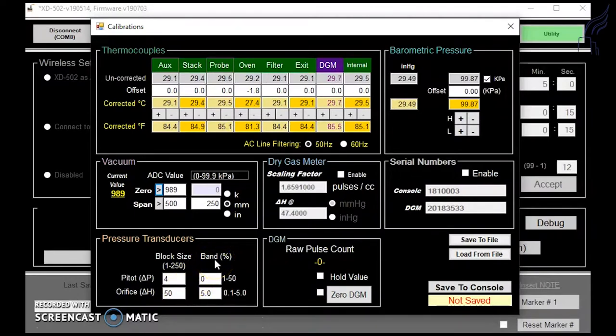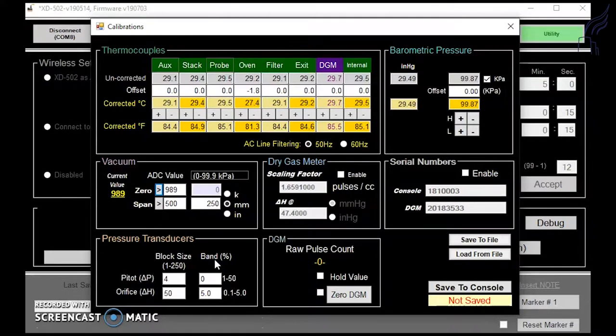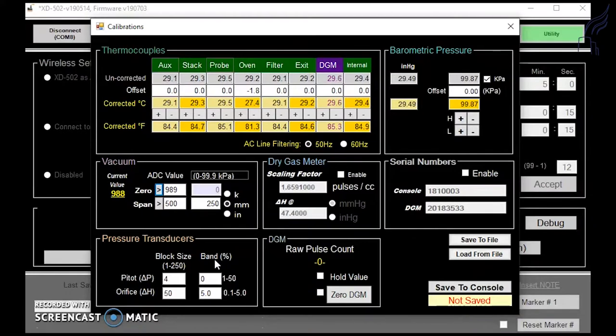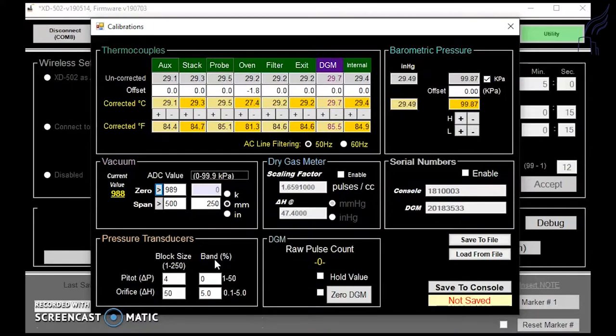For band percent, it starts a new averaging block if a value appears that is outside of the selected percentage. This is useful for when flow at a traverse point changes dramatically. As a tester, you don't want to wait four or five averaging blocks to start seeing true values.